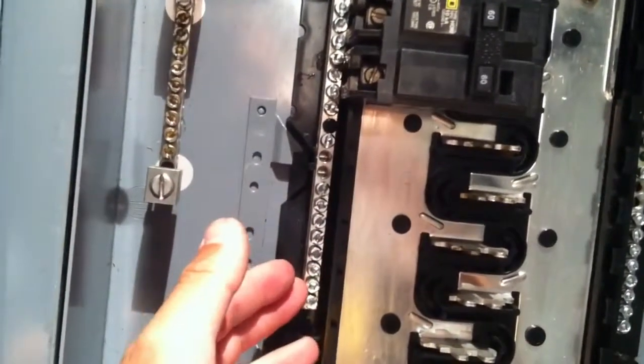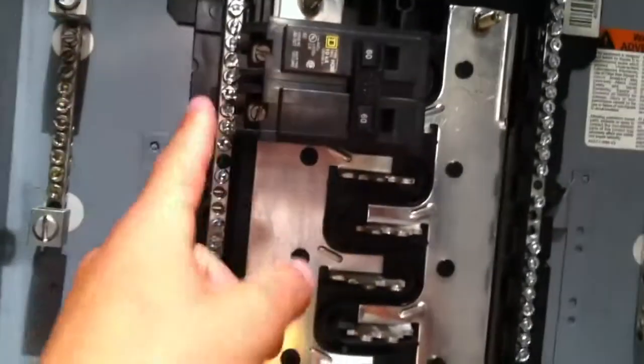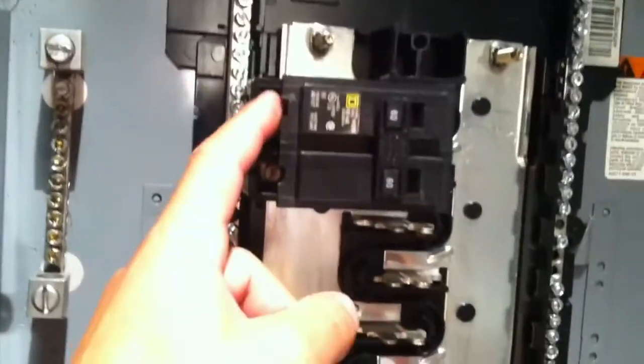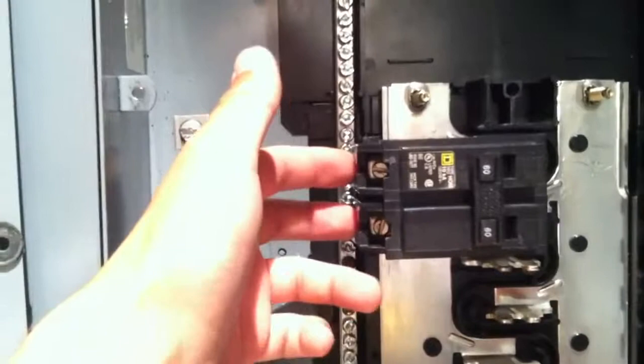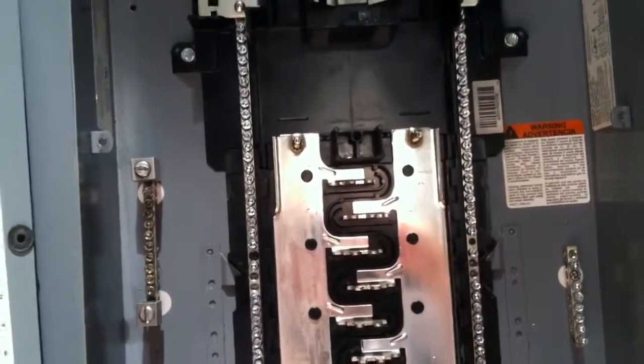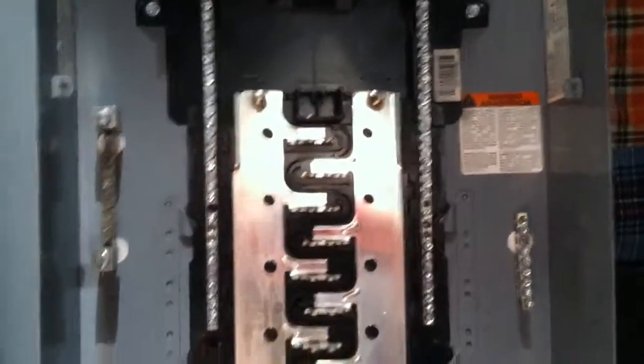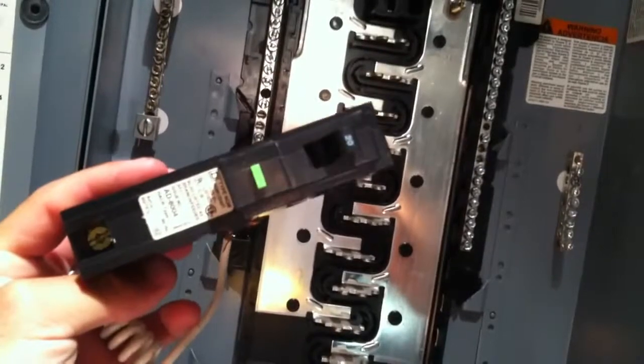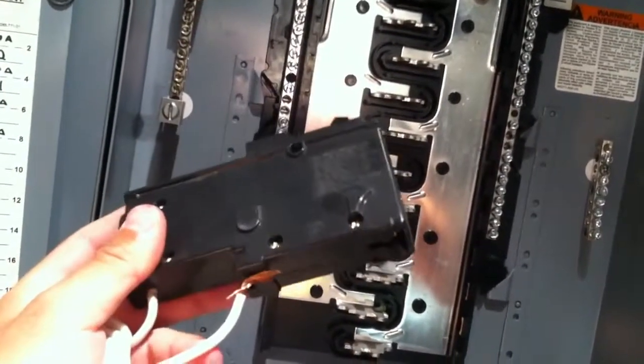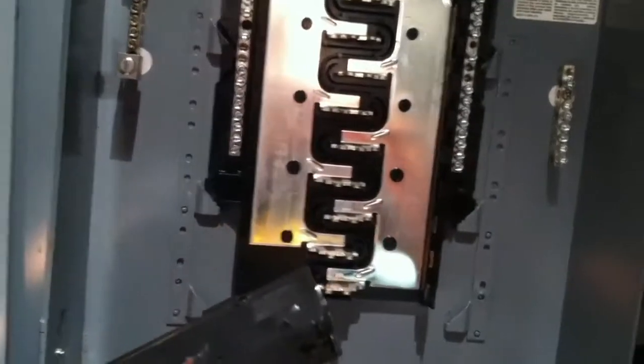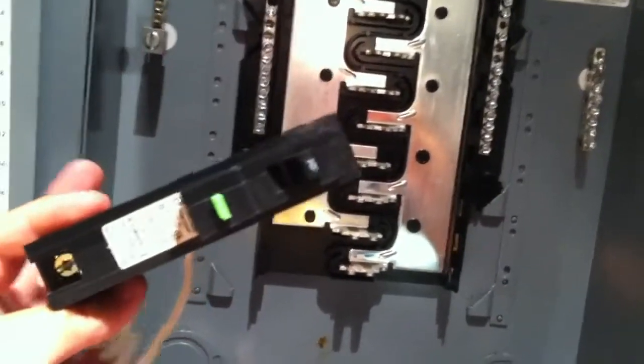Sometimes it's a smaller gauge wire because the things that do require 120 volts don't pull quite 60 amps, so it doesn't need to have that large of a neutral. In that case, you'd have a little neutral that goes along with it, and it would pull 120 volts from either of the legs to the neutral, and the main appliance that pulls the 240 would pull from both hot legs. Alright, so there's one more type of circuit breaker that is found commonly today, and that is this kind. It's an AFCI breaker. So it's typically the same as a normal breaker. It's basically the same as a normal circuit breaker, and we'll go into depth about what this is.